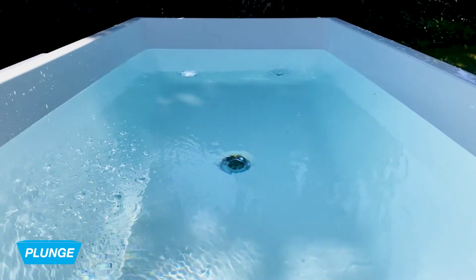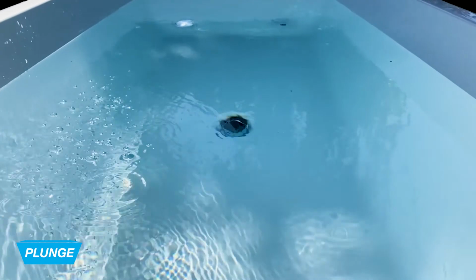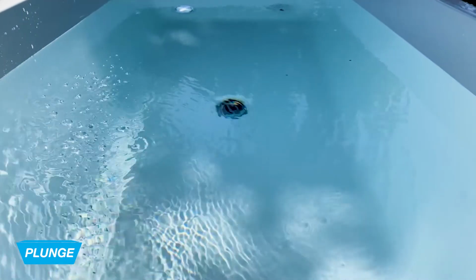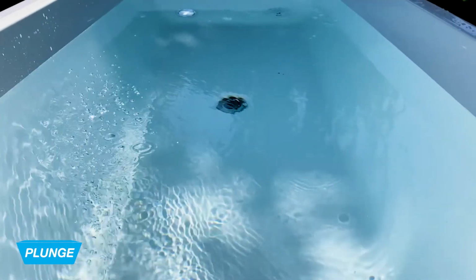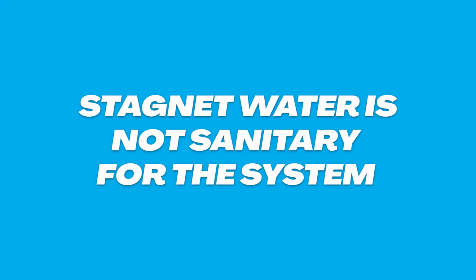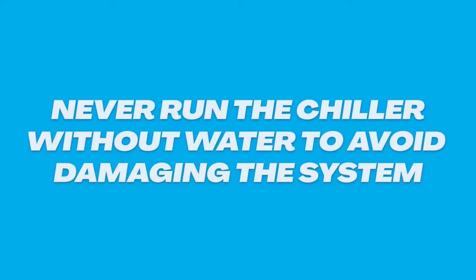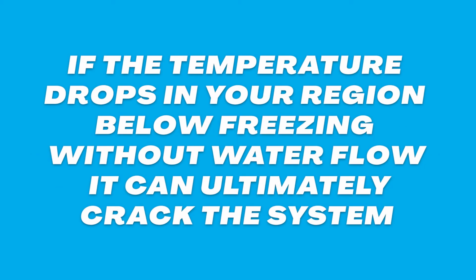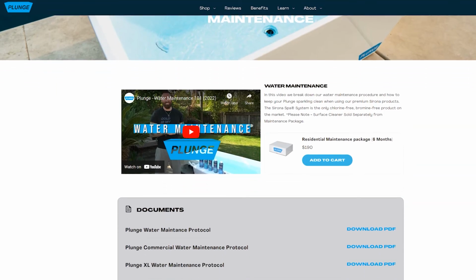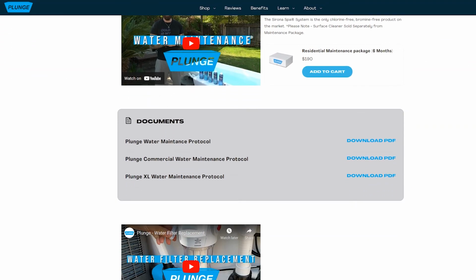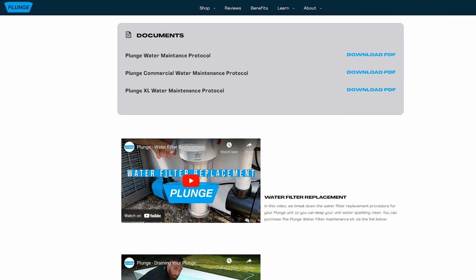The plunge is designed to have water flow 24/7. Water flow is important for these 3 reasons. Stagnant water is not sanitary for the system. If the chiller is on with no water flow, it can cause damage to your chiller. And if the temperature drops in your region below freezing with no water flow, it can ultimately crack the system. Please check out our water maintenance videos on how to maintain your unit.